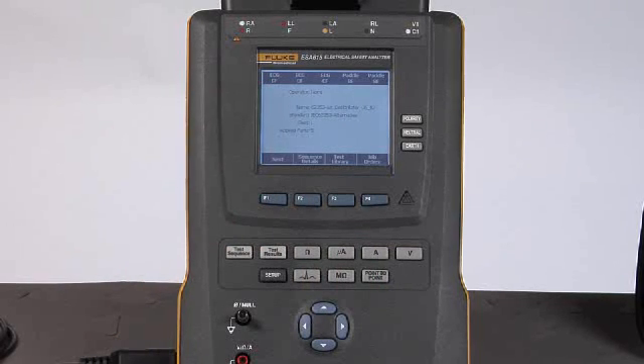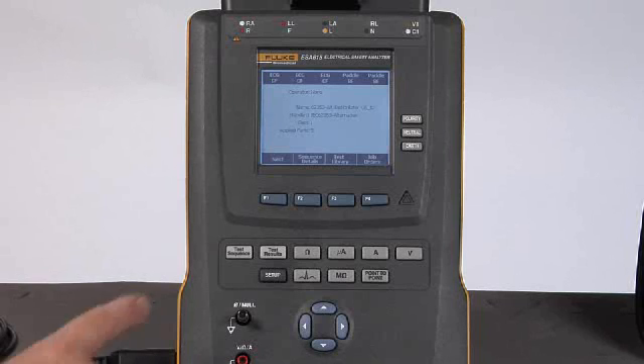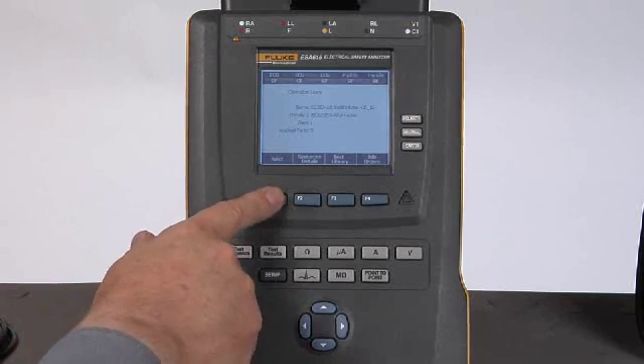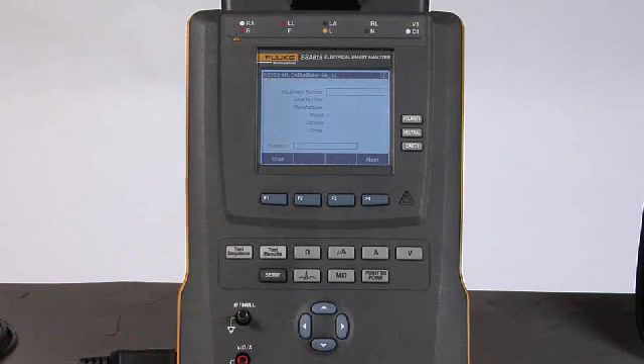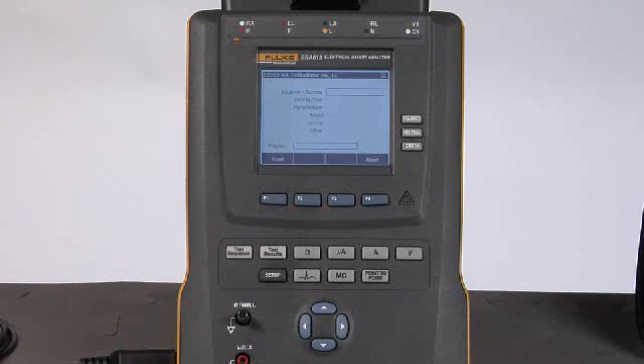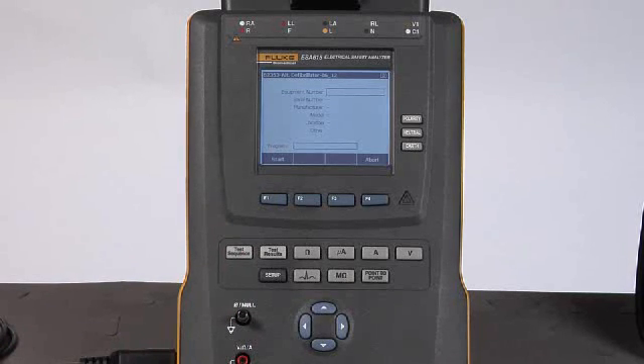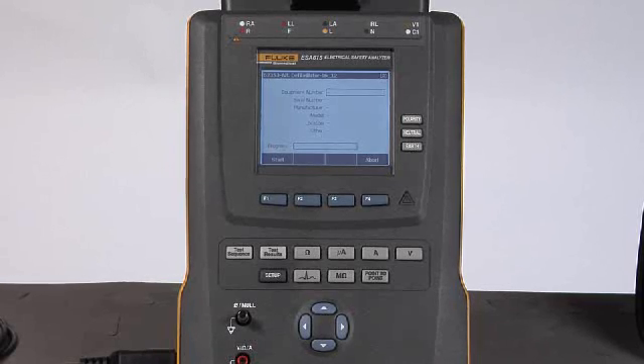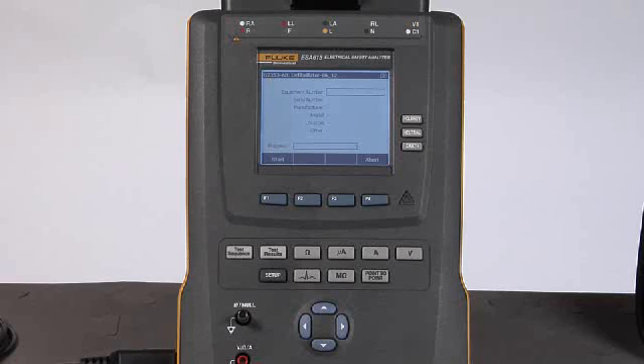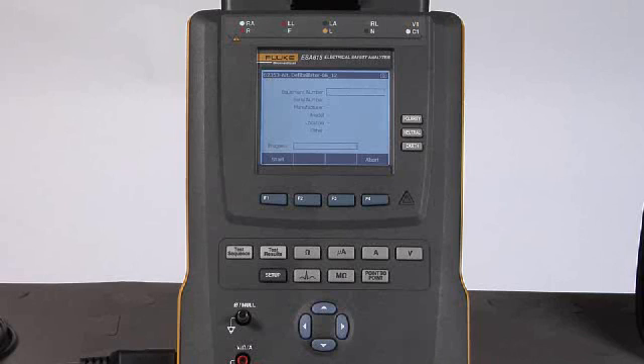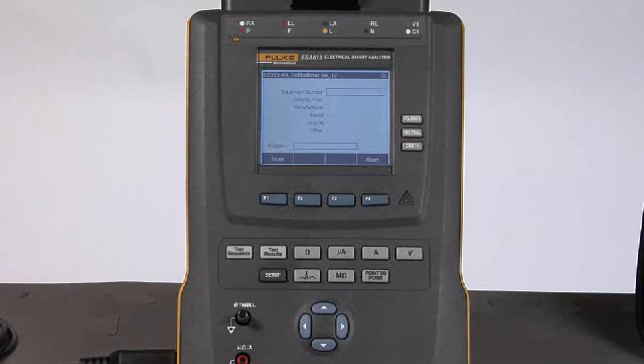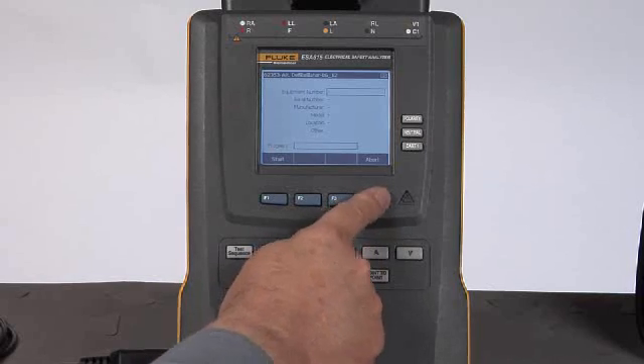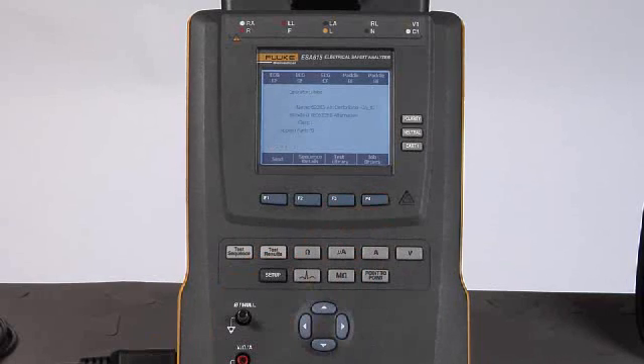If I choose to run the test sequence that I have selected, I will pick the F1 button next. And that allows me to enter the device under test information, including the location, whether it be on a particular part of the hospital or in another building on campus or across town. And once I have done that, then I would press the start button to actually run the test sequence. We'll leave that for now.